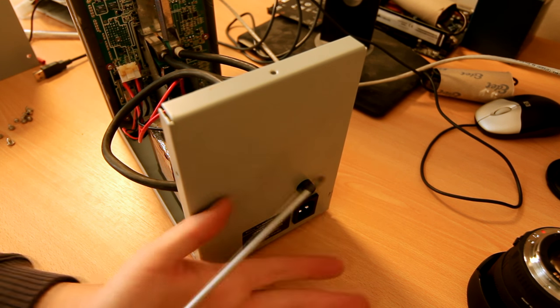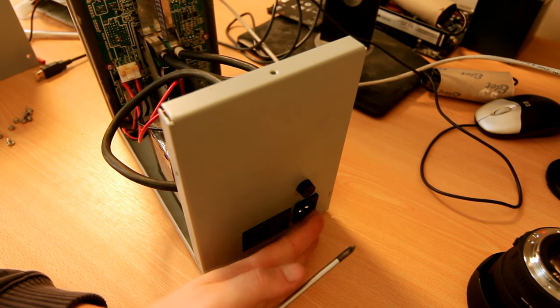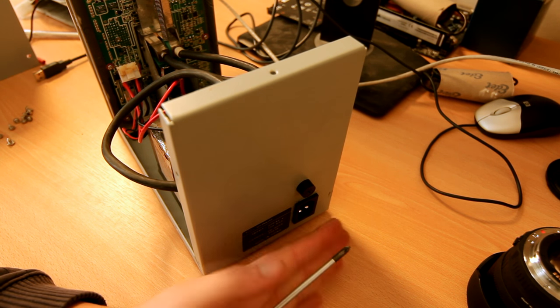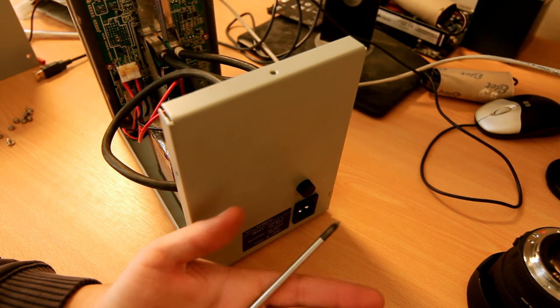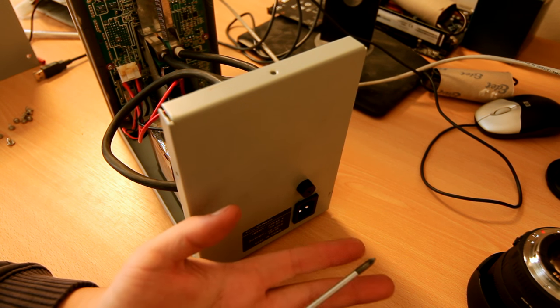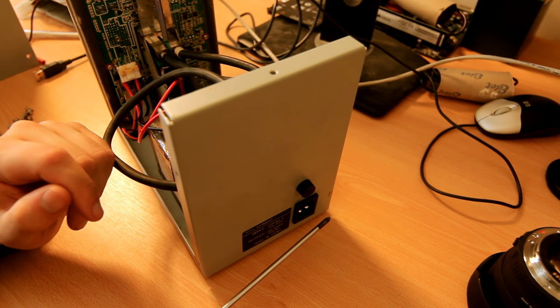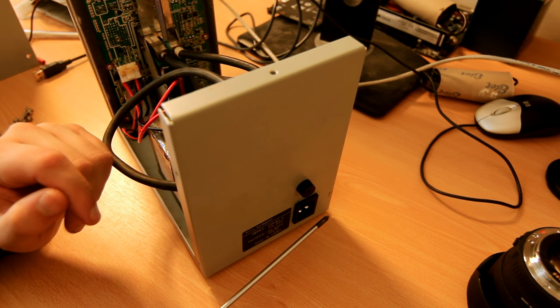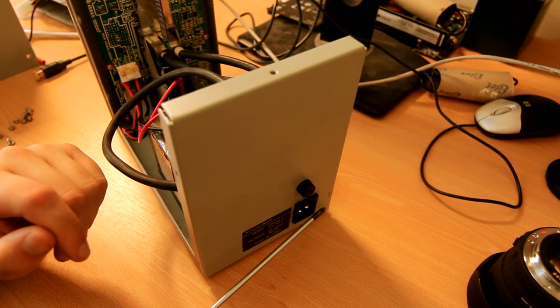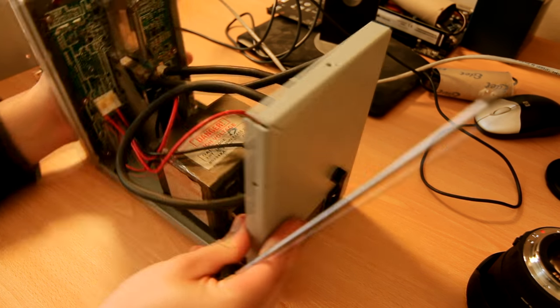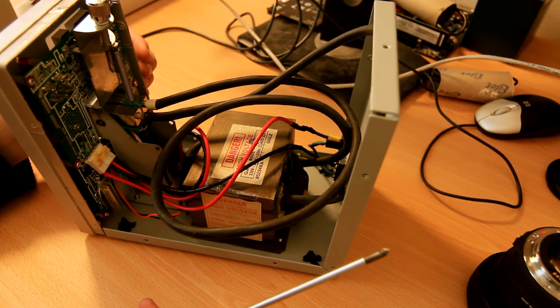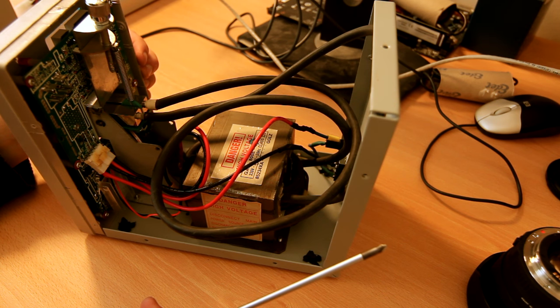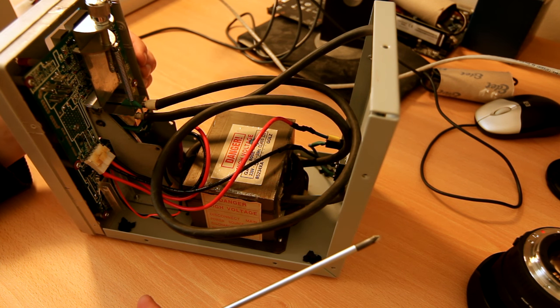You cannot make equipment that draws more than 16 amps and outfit it with this socket, because the cables are interchangeable and you only get 16 amp cables. That's a very worthwhile improvement. Otherwise, it's just the transformer and the IEC socket.